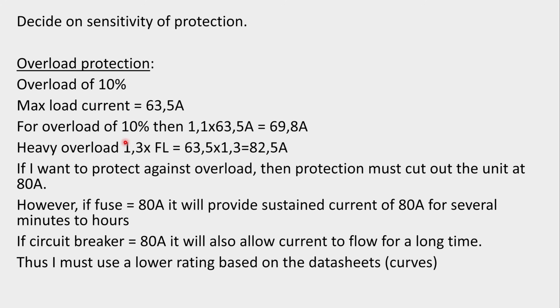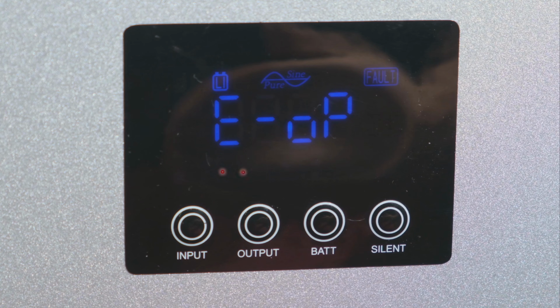Now let's take an even higher overload. Here we have a 30% overload, so it's 1.3 times the full load current. Notice that the current is now above 80 amps. Now that is a much higher current, and we probably find that this inverter would overheat and break. But this is where one needs to know the device that they're protecting. I know that the inverter does have its own internal protection system to stop this from happening. For example, here's the screen of the inverter when I overload it beyond its capability. It does go into a fault mode, cuts off the output, and I have to power down the inverter and restart it, and then it'll allow me to feed my load again.